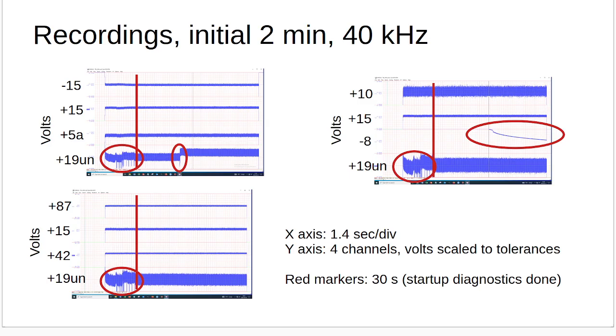Now, the +10, the +15, the -8, in fact all the channels here, are scaled to the tolerances that I showed you for table 5.1. And the only one that you don't see coming into range where it should be is the -8 channel. Now, I believe that this could be an explanation for things like a test 05 fail 40 error. You'll notice that it never gets down to -8, which means it's a higher voltage than it should be. Okay, test 05 fail 40 means unexpectedly high voltage, or inappropriately high voltage somewhere, and that might be the explanation, maybe.